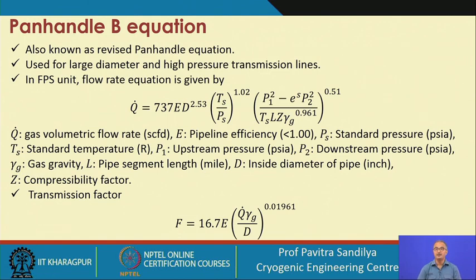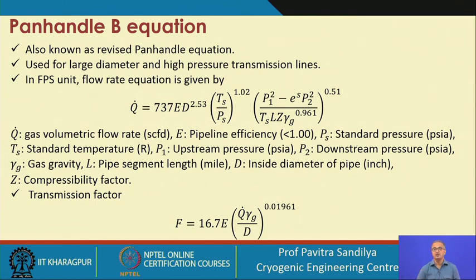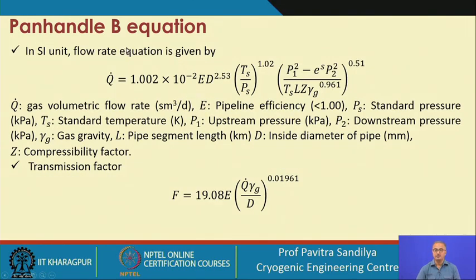We have another equation called the Panhandle B equation, which is a revised form of Panhandle A. It is generally used for large diameter and high pressure transmission lines. In the FPS system, the Panhandle B equation has the same basic structure as Panhandle A — the differences come only in the values of the various coefficients. These values have changed because some additional physics have been taken into account. The transmission factor expression is given, and similarly we have the Panhandle B equation for SI units.